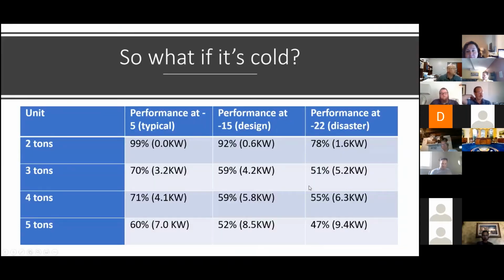So now, it's going to get cold per our earlier slide where we showed that polar vortex. Can we rely on the compressor alone? Not according to our design conditions. If we're at 2 tons and we're at minus 5, we will have 99% of the heating capacity, which is fantastic. And maybe at that you go, all right, if our design condition was minus 5, I'm fine with no trim heat.